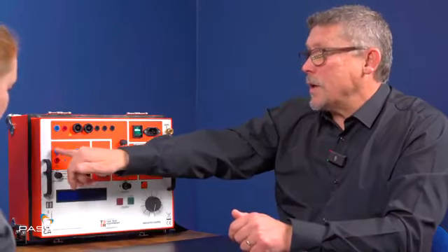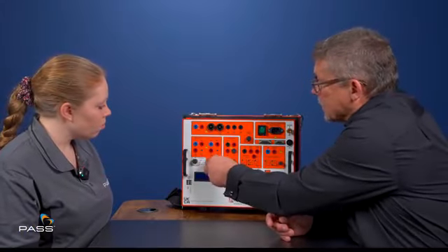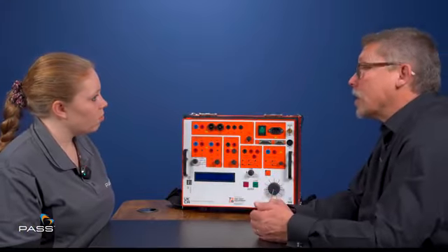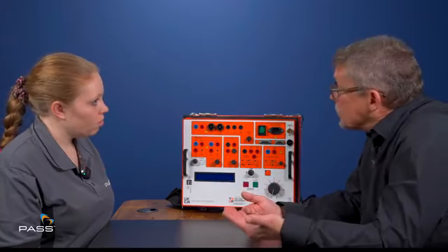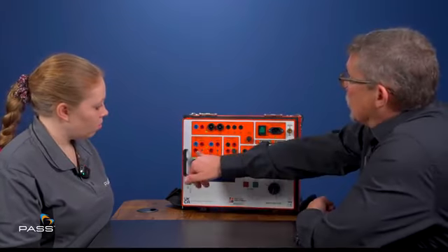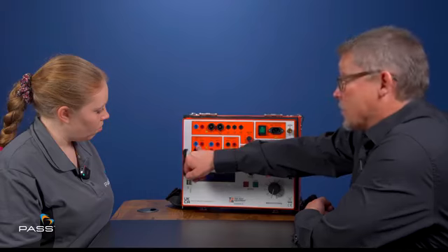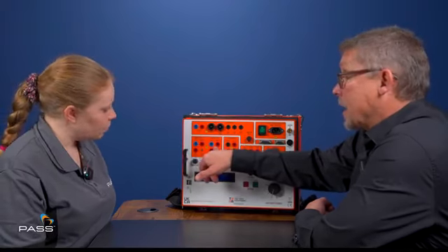Now on one contact, that would be for a relay where even when you put the current out, the relay's not made. So you put the current out, you shut the relay. Now the minute I shut the relay, it sees a change in state here. So it starts the timer. When the relay is then operated, it will see a change of state here and stop the timer. And that's with one contact. If we've got a relay that's got a start-stop dedicated contact, we go to the 2 contacts. And in 2 contacts, generally speaking, it starts the timer here, stops the timer there.